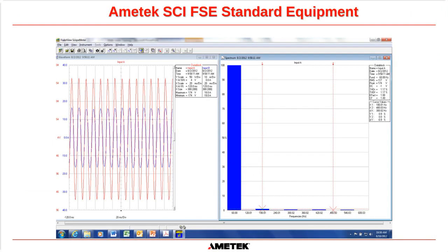And with the Fluke 190s, what we can also do, if absolutely necessary, if we think there is some kind of electrical distortion on the output of the system, is check the THD, the total harmonic distortion of the output waveform. You can see on the left-hand side, the red waveform is the output voltage of the system. And then the Fluke software has the ability to use a spectrum analyzer on that signal, and therefore we can look at the harmonics involved. On the right-hand side, we can see that the THD for that waveform is 1.17%, and that's well within the specs of the system.